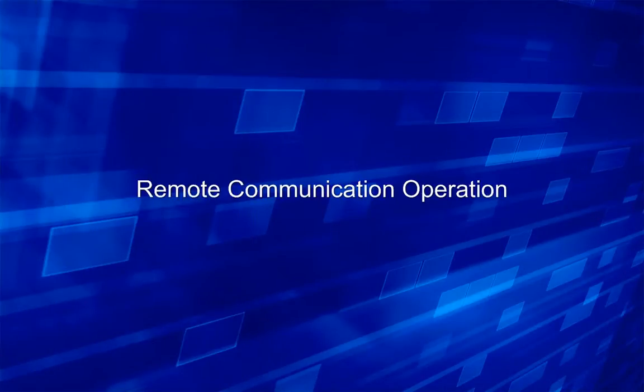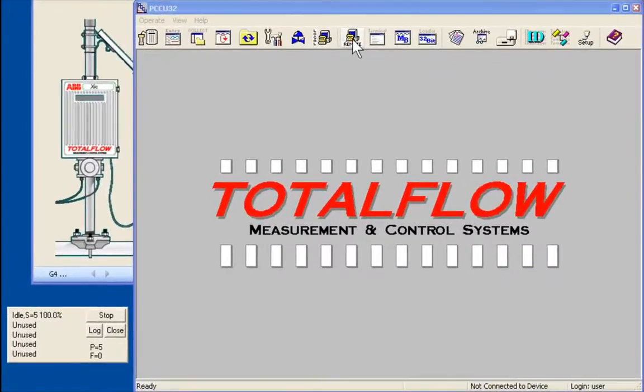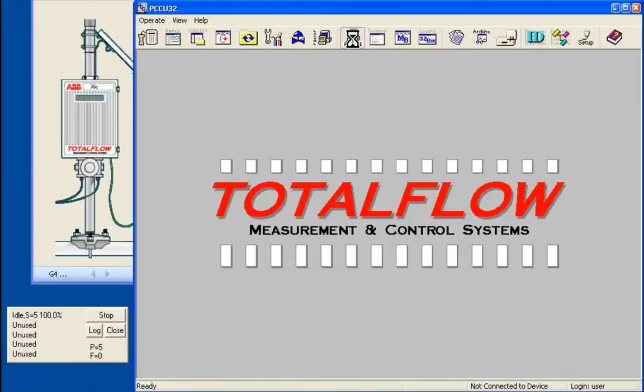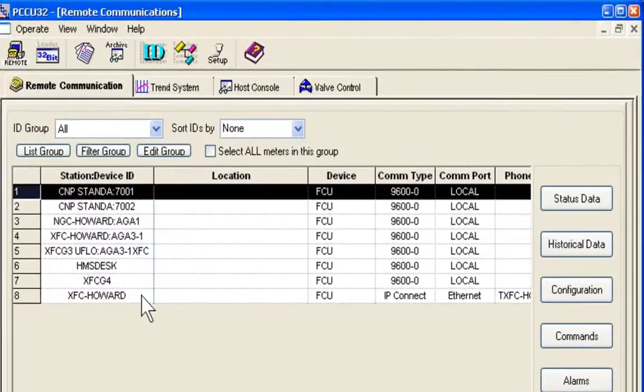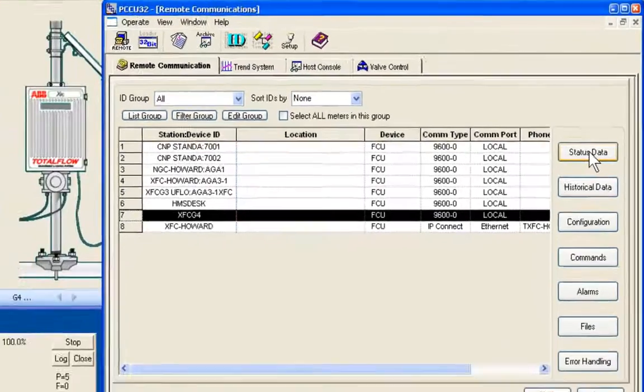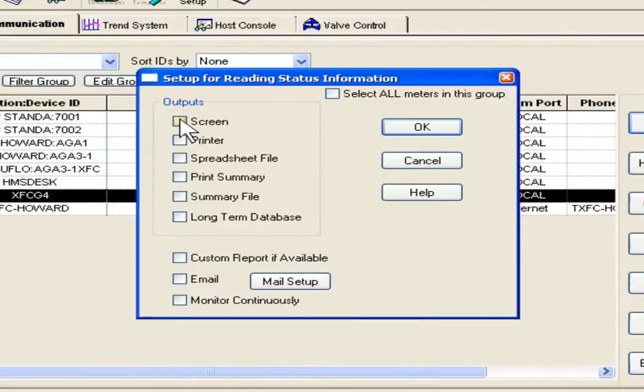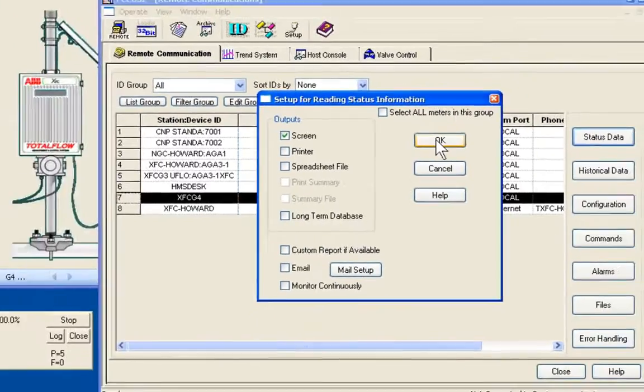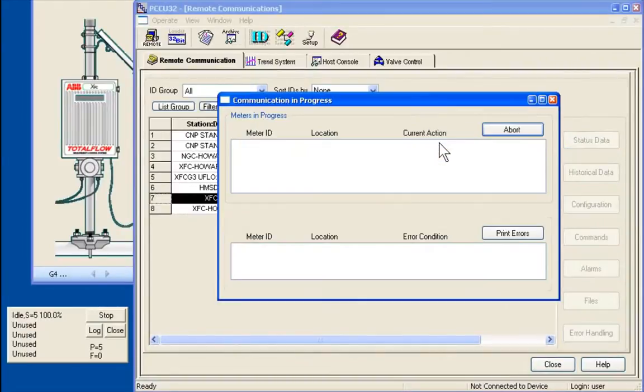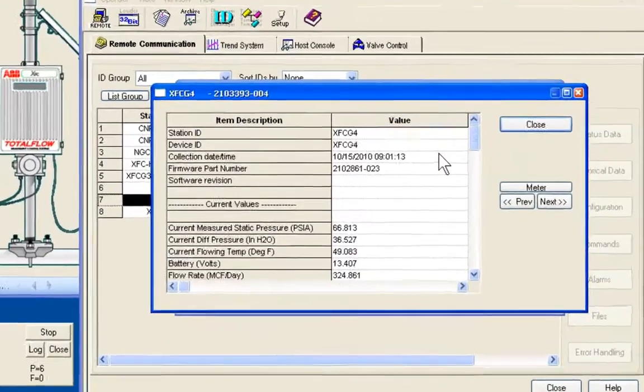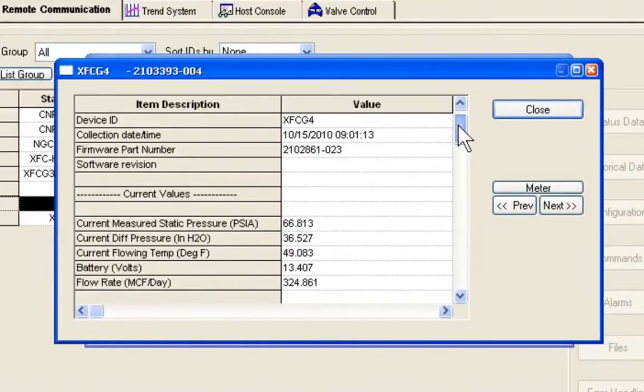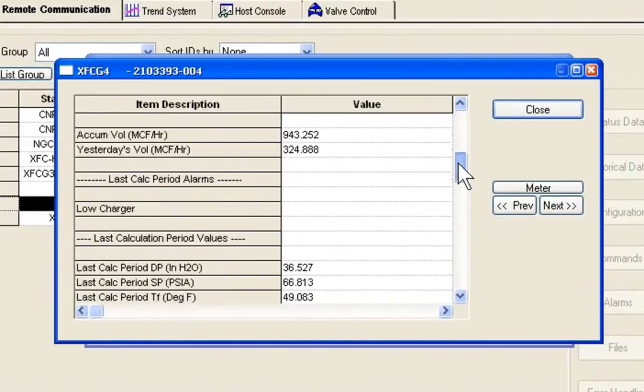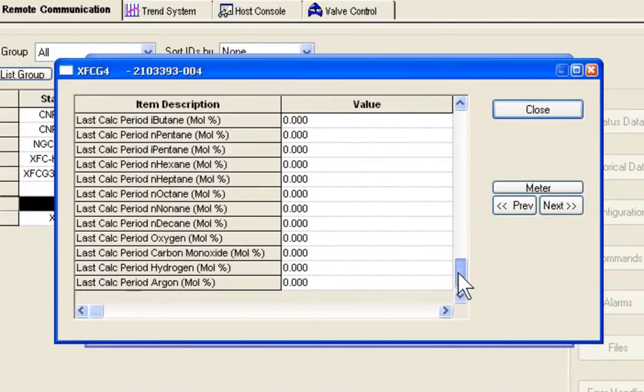We're now ready to connect the G4 with the PCCU host. First we select the remote communications icon at the top of the screen. This brings up our list of IDs. We'll pick our ID that we set up before. We're going to do a status poll. We'll pick status. And we're just going to place the data on the screen, as you can see here. We'll say OK. And quickly we'll receive our communication back with polled data. As you can see here, this is the data that is brought back with a standard poll.